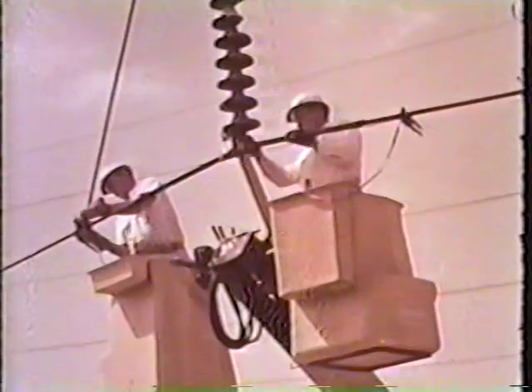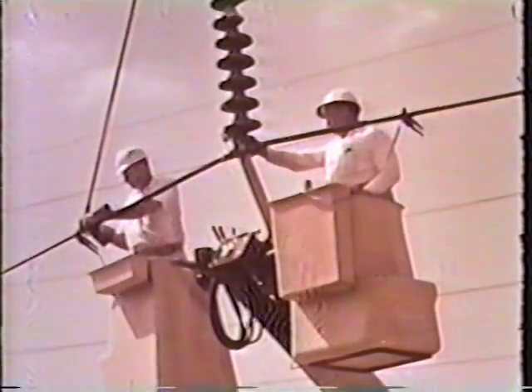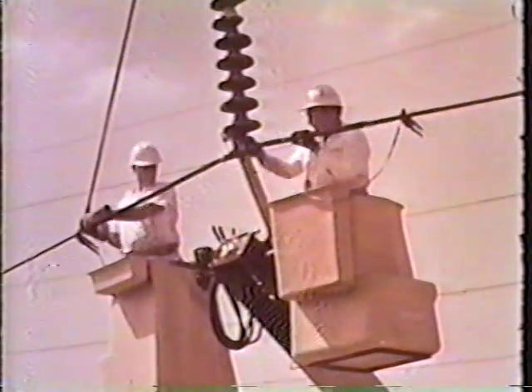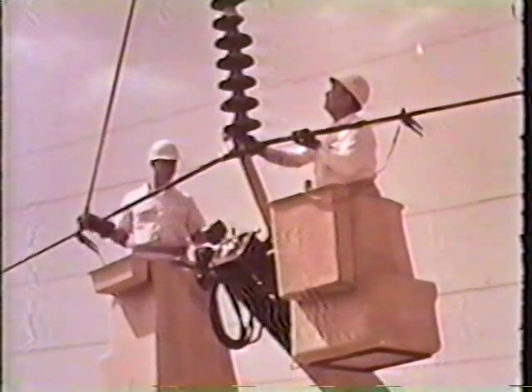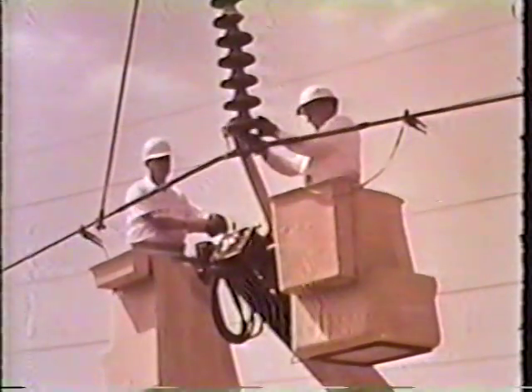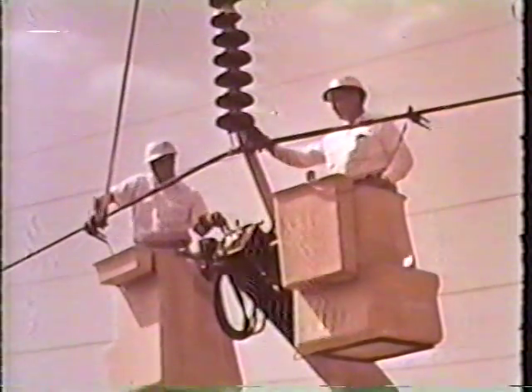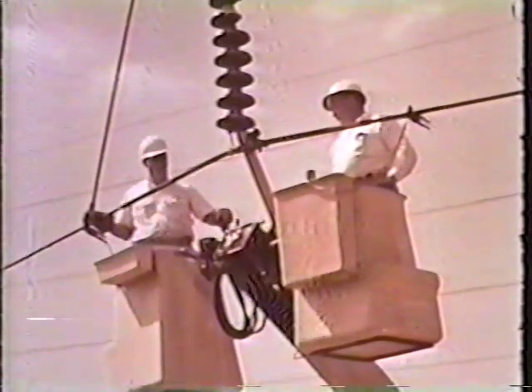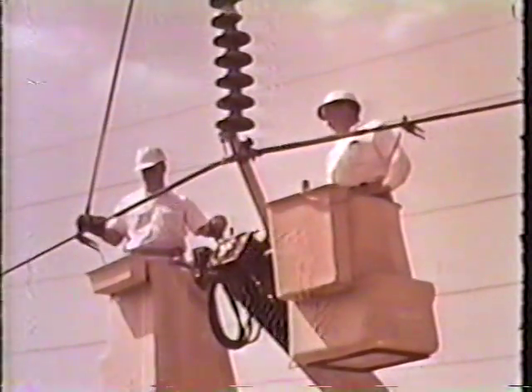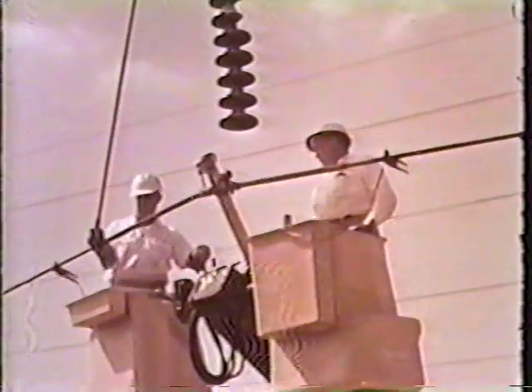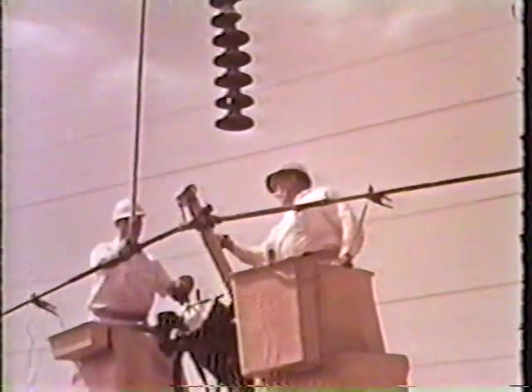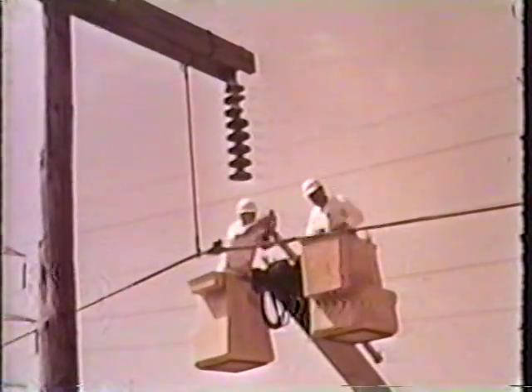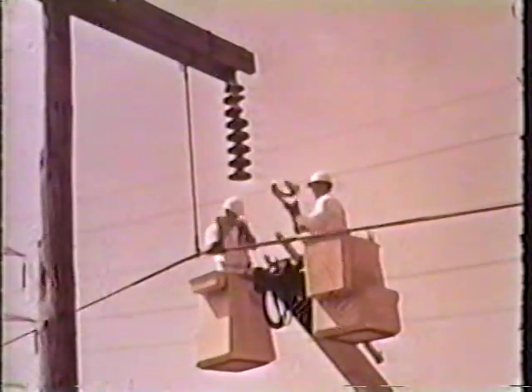Doing the work is the small fiberglass boom mounted between the buckets. The boom has the same insulating quality as the arm itself and can be pivoted vertically and extended up to 6 feet in length. After the link stick is attached, the insulator string is disengaged and the conductor is lowered to the support of the link stick. Full feathering hydraulic controls have a firm, precise feel, allow smooth, gentle movements, and pinpoint positioning.